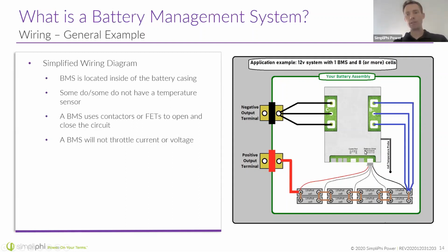What you see coming out down here are the balancing wires. This is only a 12-volt system if we're looking at LFP cells, so it's a 12-volt battery, which is a 4S unit. So what does the battery do? Many people have misconceptions about what the BMS can do. The battery management system cannot throttle the current back, it has no means of limiting its current to a certain value. One thing it can do is open or close a contactor, which lets the battery isolate itself from an unsafe system, but it doesn't have individual controls. There's no mechanism by which the battery can do that.